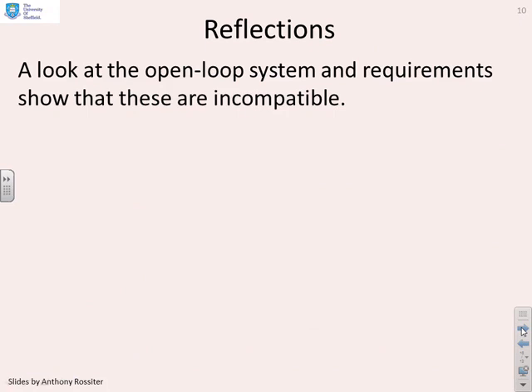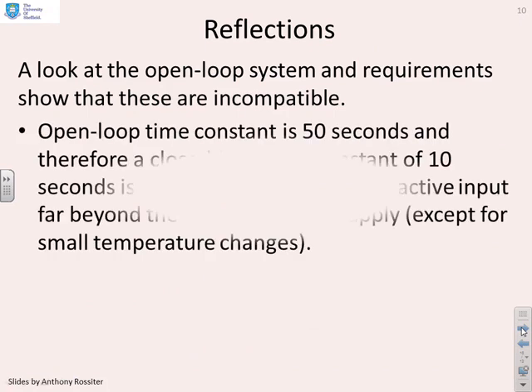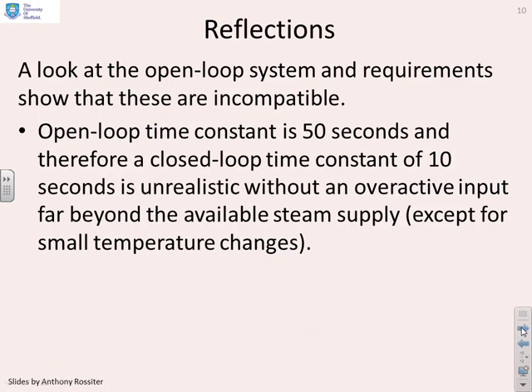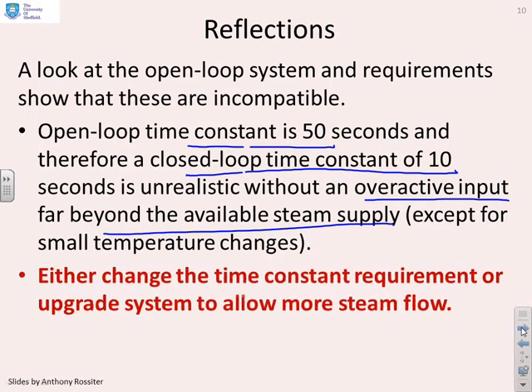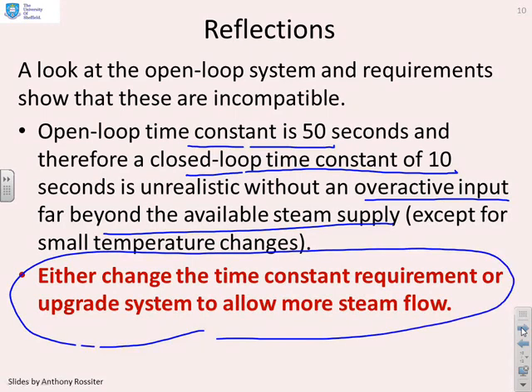What does this tell us? If we look at the open loop system and the requirements, we see they're incompatible. The open loop time constant is 50 seconds and therefore if we want a closed loop time constant of 10 seconds, the only way we can achieve this is with an overactive input. At the moment that's far beyond the available steam supply, unless you're just asking for very small temperature changes. You have a choice: either change the time constant requirement and accept that this heat exchanger has to have a slower time constant, or you have to upgrade your system in order to allow more steam flow.